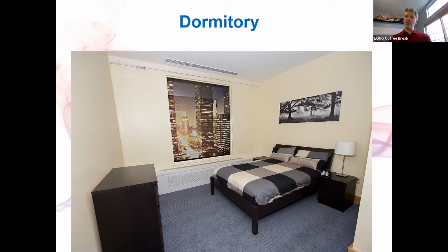And in general, we look at all these things when we're trying to put the system together, because the amount of air that you're supplying to the beam, the temperature of that air that you're supplying to the beam, which helps with any dehumidification load that you have, the chilled water temperature, the hot water temperature, all these have a great effect on what the chilled beam actually produces. And the nice thing that the Dadanco can provide to you is a spreadsheet that is just amazing.